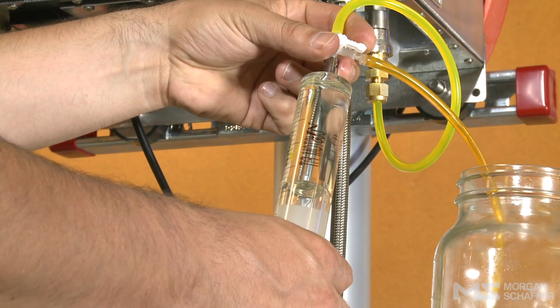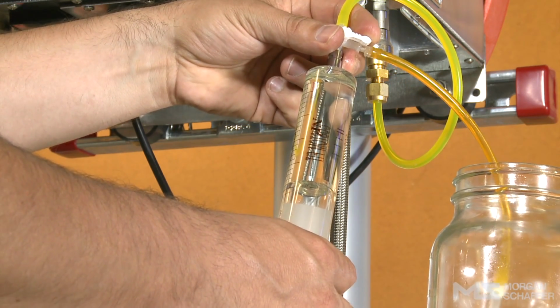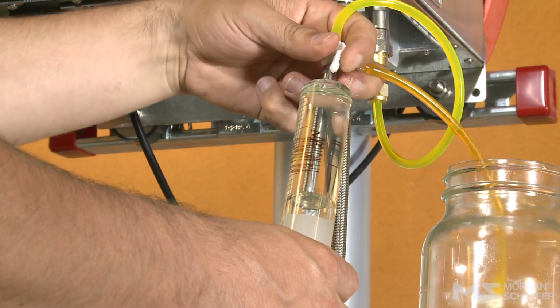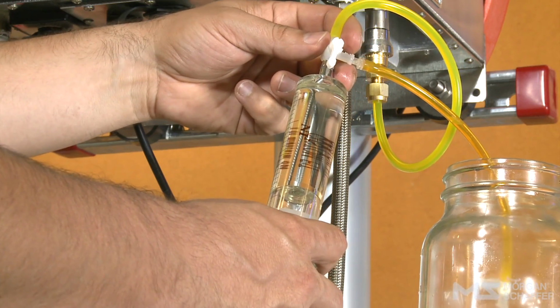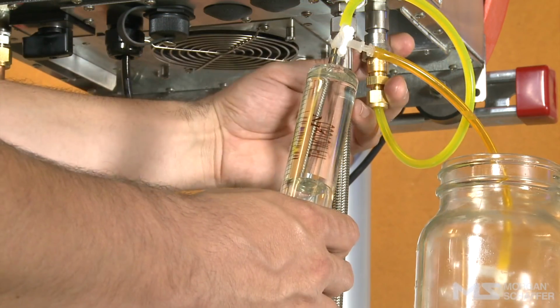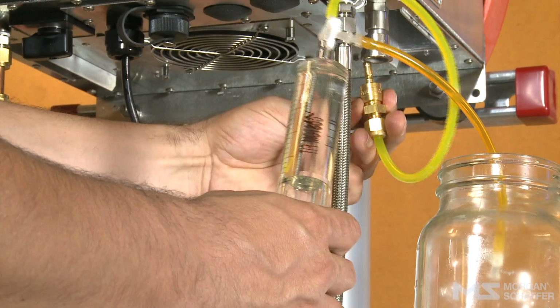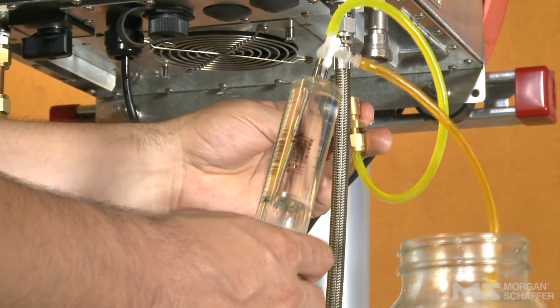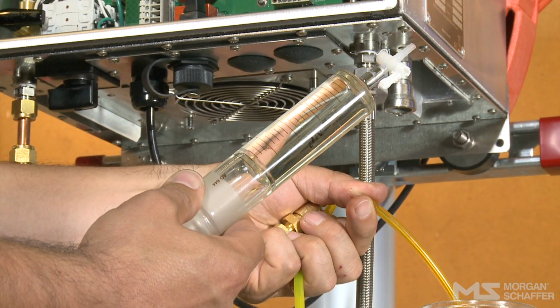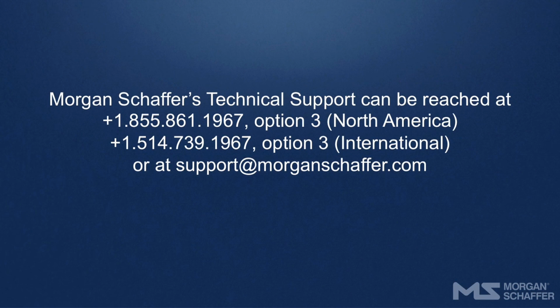Once the desired volume of oil has been reached, close the shutoff valve of the syringe, handle toward the syringe, then remove the syringe and the oil sampling tube. The oil sample is ready for analysis. The installation and commissioning of the Calisto 2 online DGA monitor is now complete.